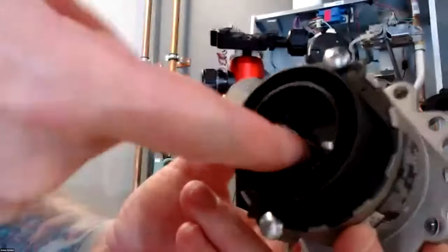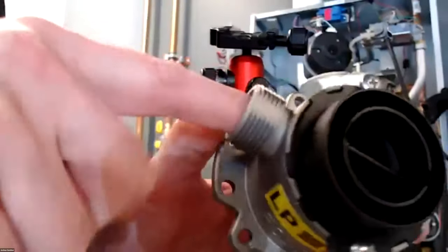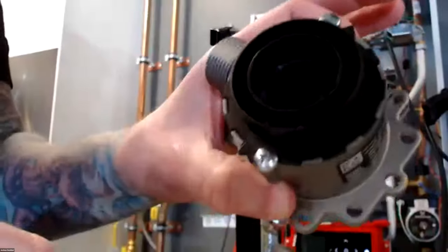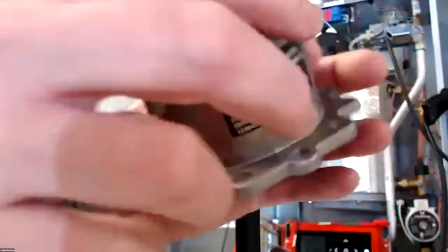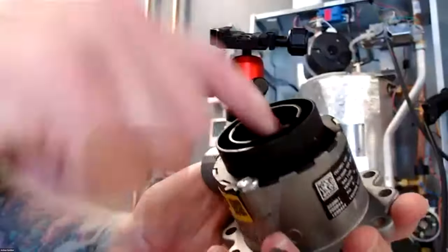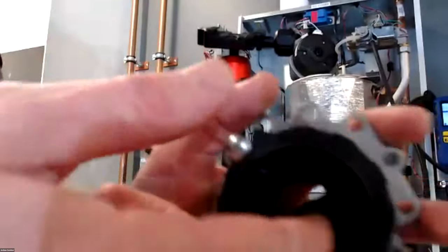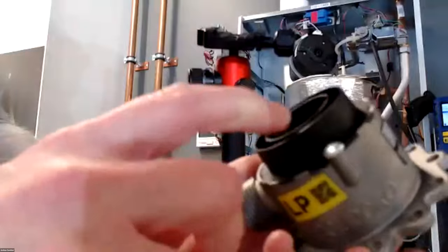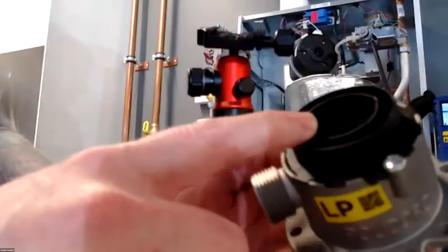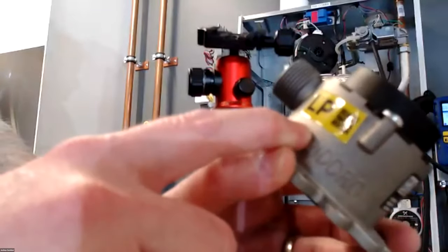So our air is coming in through right here. There's a couple dampers in here, and you can see there's a damper on the boiler side. And our gas comes in through here. There's two orifices on the top and bottom. This is a sealed unit. So if we get debris in here, leaves, this can stick up. So on some service calls for no heat, check that venting if you think you got debris in there. This is where it tends to usually get caught up, right? And this is pretty much the only thing we change on the conversions.